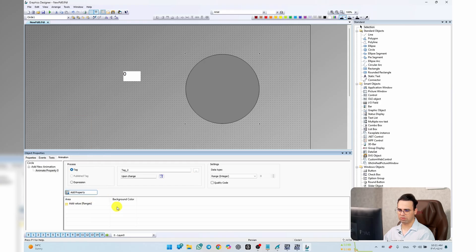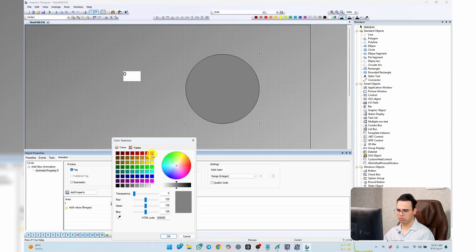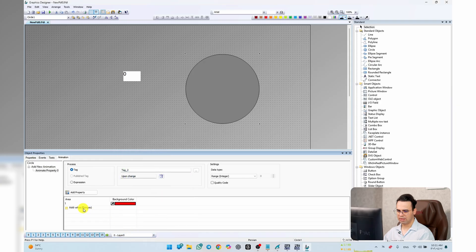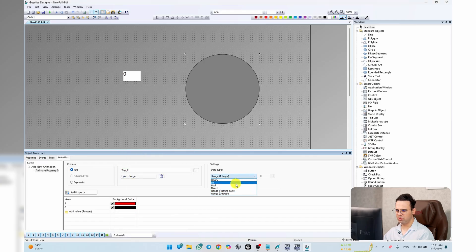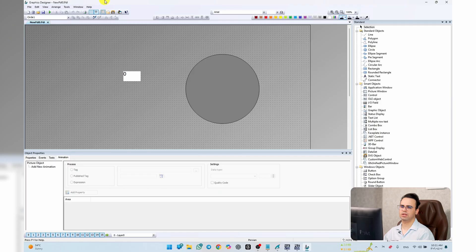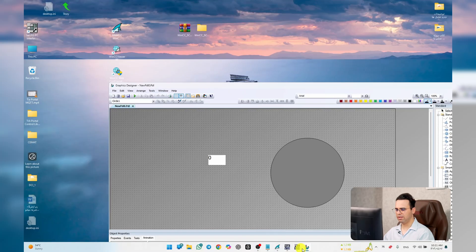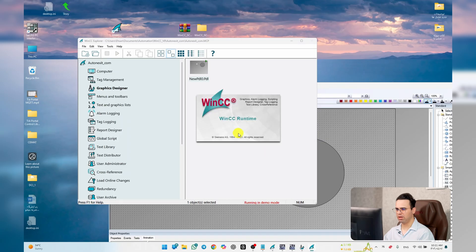Set the process tag to Tag Two, trigger on change, and hit OK. Add values: if it goes to 1, change the background color to red; if it goes to 0, change it to black. Since it's a Boolean — true or false — that's it. Save it and run the project.